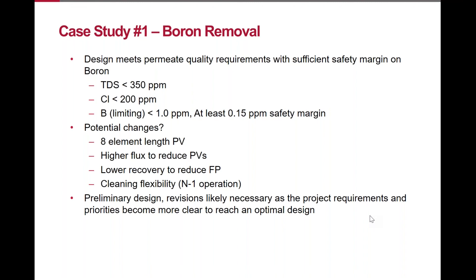Additional considerations include whether the client wants cleaning flexibility, which would require accounting for N-1 operation when sizing pumps. N-1 operation increases maximum feed pressure, while worst-case quality corresponds to end-trains operation. This is a preliminary design — revisions are expected after discussion with the end user to understand priorities. For example, increasing flux to reduce pressure vessels if capital cost is a concern, or lowering recovery to reduce feed pressure if that's the priority.